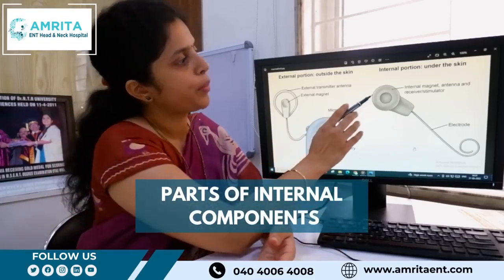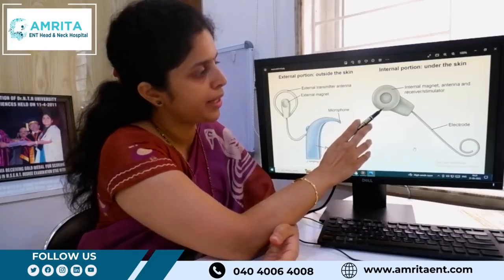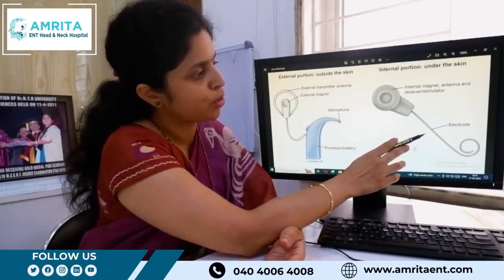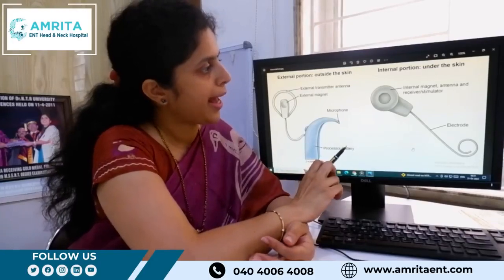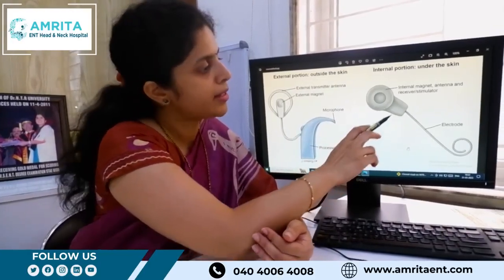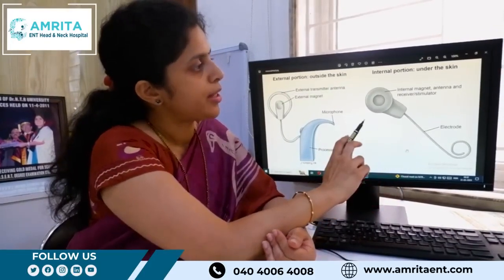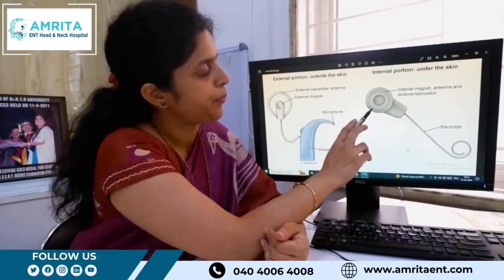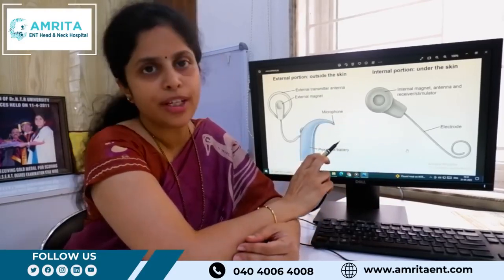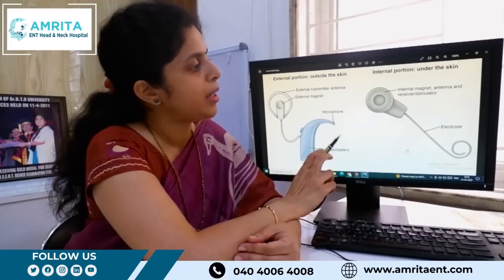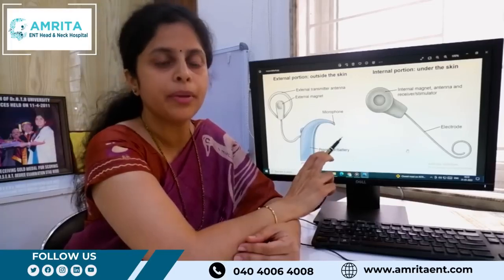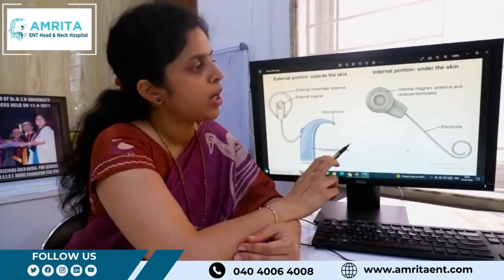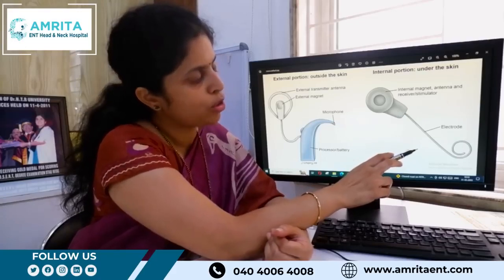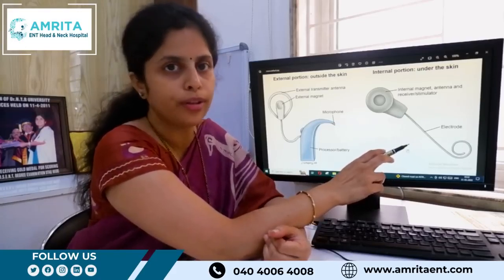The internal component has a receiver or stimulator and an electrode array. The receiver or stimulator has a magnet, and the surgeon makes an incision behind the ear and implants the receiver or stimulator between the skin and the bone, and meticulously inserts the electrode array into the cochlea after doing the cochleostomy.